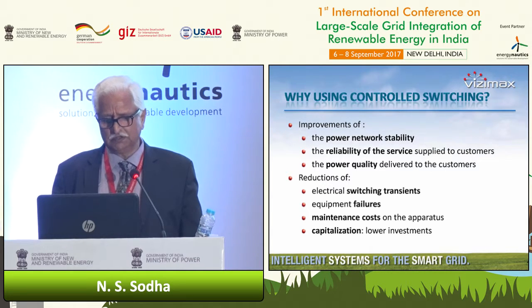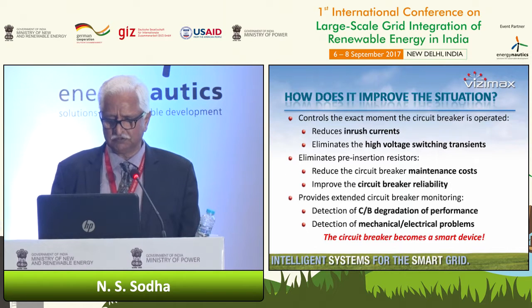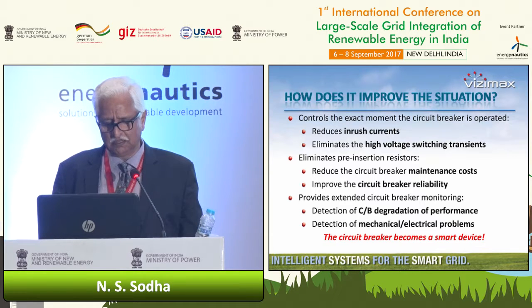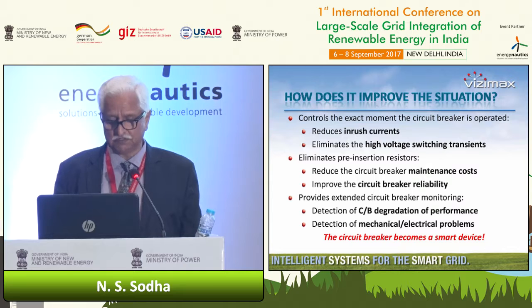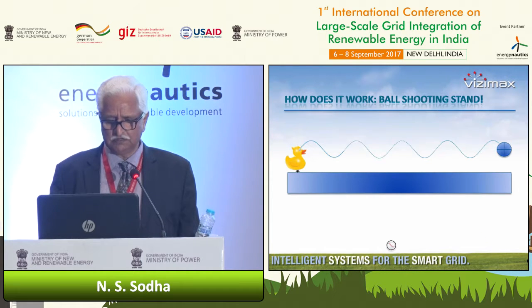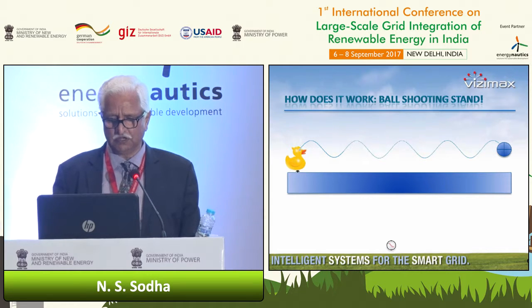Similarly, how does it improve the situation? It controls the exact moment the circuit breaker is operated and eliminates the high voltage switching transients. And if you look at the overall picture, the circuit breaker becomes a smart device. Now it is like shooting a duck: if the duck is moving, the ball has to hit the duck at the right point.